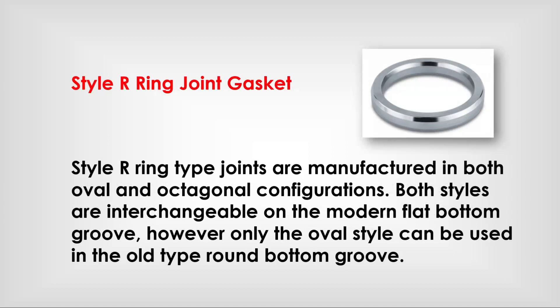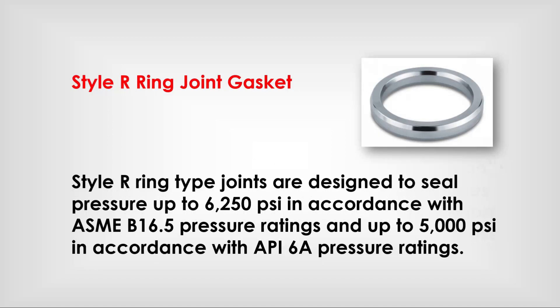Style R ring-type joints are manufactured in both oval and octagonal configurations. Both styles are interchangeable on the modern flat-bottom groove; however, only the oval style can be used in the old-type round-bottom groove. Style R ring-type joints are designed to seal pressure up to 6,250 psi per ASME B16.5 pressure ratings and up to 5,000 psi per API 6A pressure ratings.